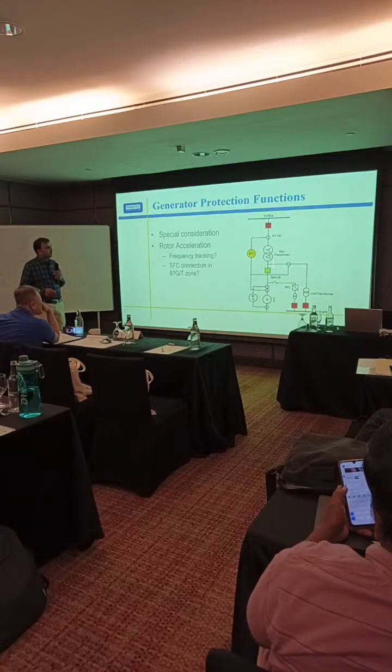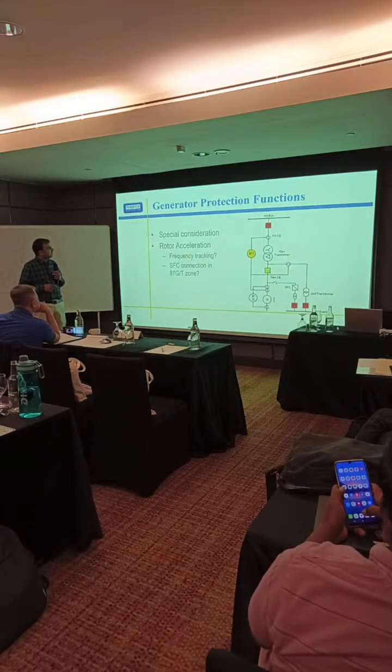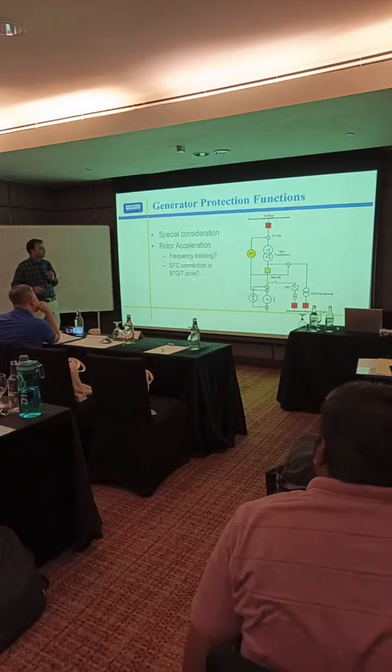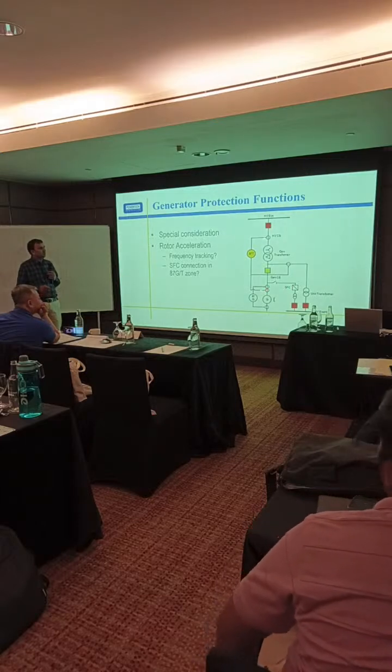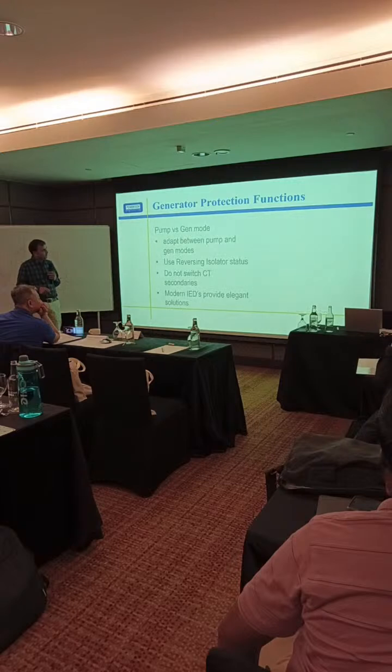because the current is different and it is also connected to the other thing, this differential may operate during starting in these conditions. That is why, during the rotor acceleration, the static frequency converter which is connected here, this current will create a fault condition in this case. That is why there is an option.